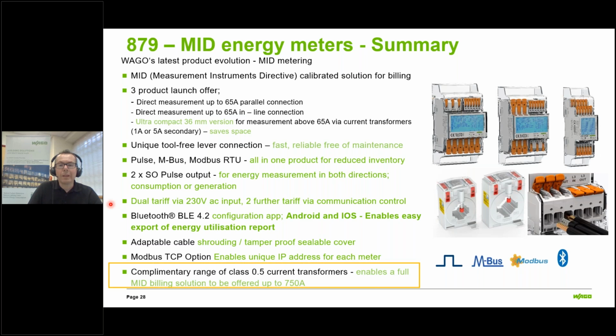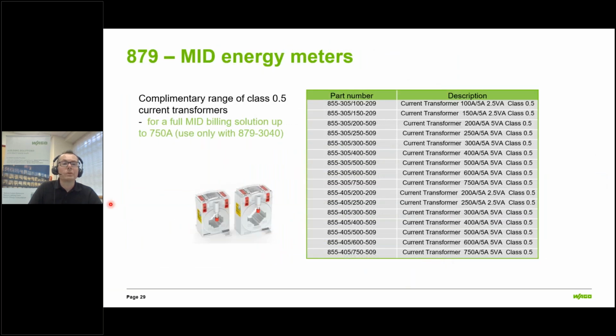And then we also have current transformers up to 750 amps for MID billing purposes. You can only use solid core CTs for billing, partly because they can't easily be removed, but also to get the accuracy of 0.5 class, which is what is specified. It's only possible with a solid core.